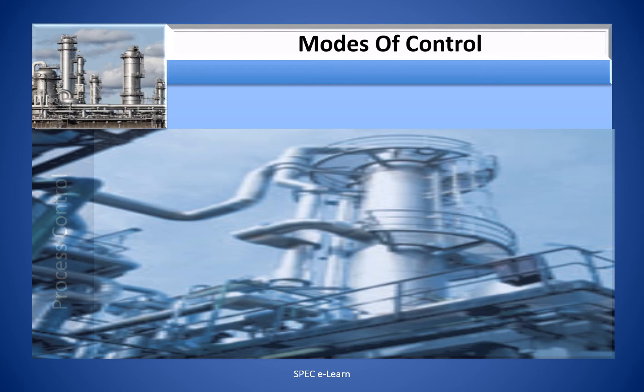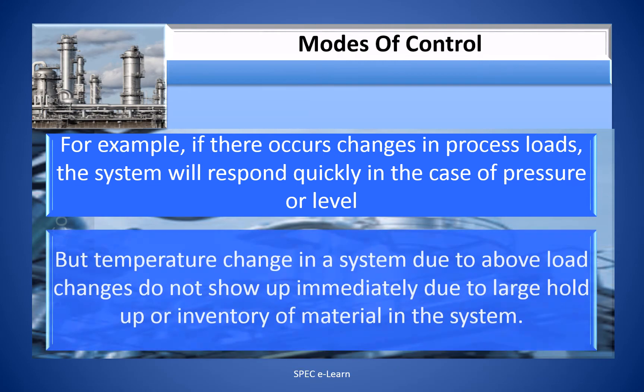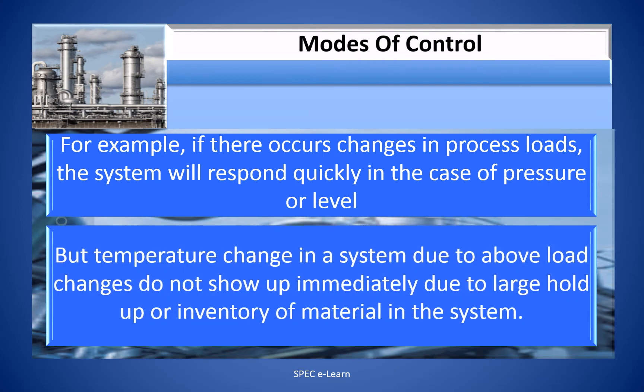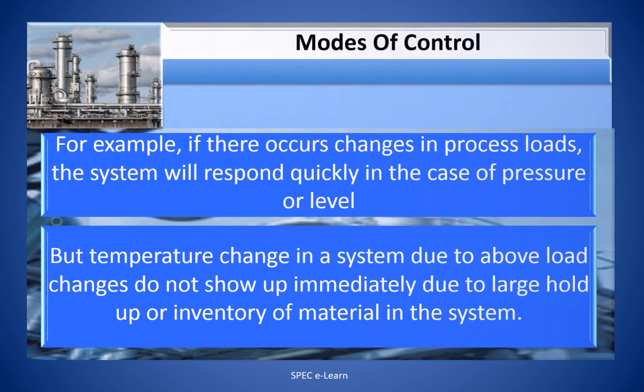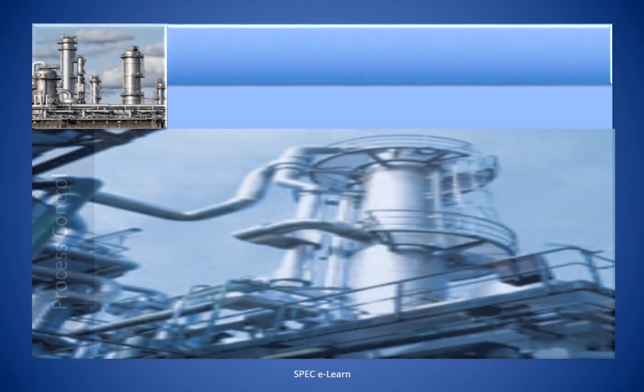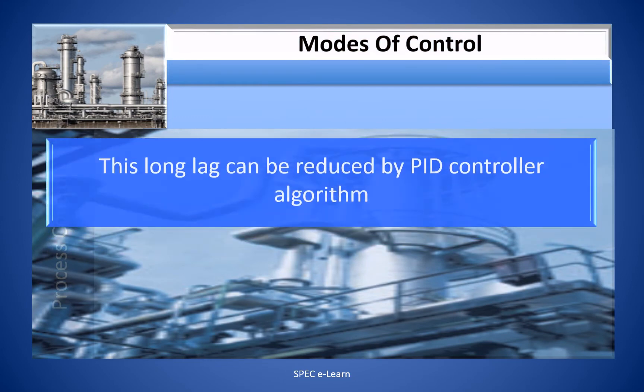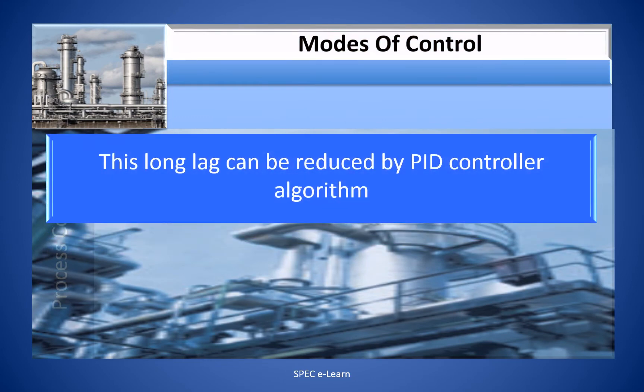For example, if there occur changes in process loads, the system will respond quickly in the case of pressure and level, but temperature change in a system due to those load changes does not show up immediately due to the large hold-up of inventory or material in the system. This long lag can be reduced by the PID control algorithm.